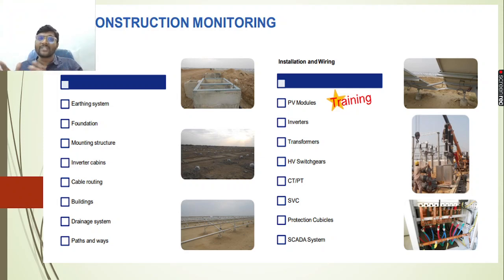Is there any path or way to take away the water being collected because of the rain? Since these are equipments installed externally, there is a possibility for rainwater leakage to get inside the equipments. So we need to make sure that whatever water flows over the systems is taken away to particular storage tanks, because that water can be used for future maintenance and cleaning purposes also.